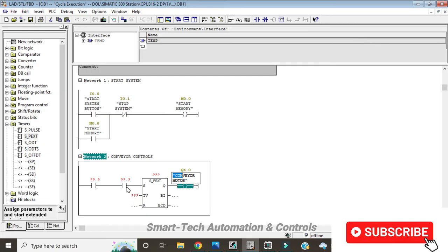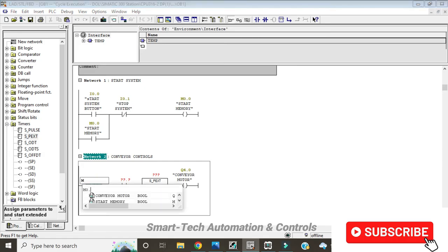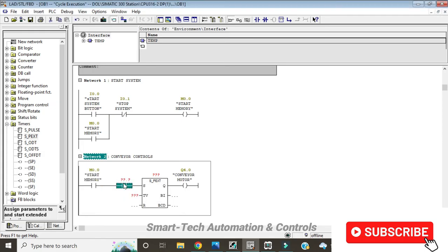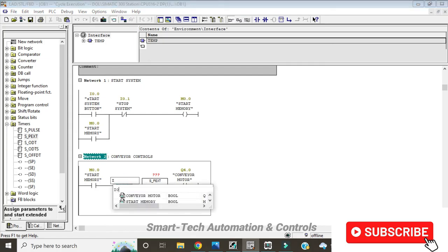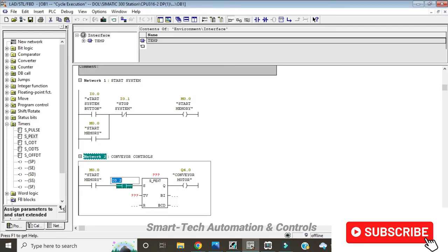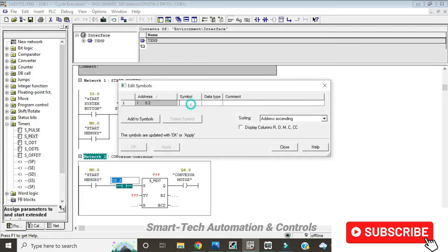These two normally open contacts will be the conditions which must be fulfilled before the timer gets activated and the motor starts. The first condition here will be the start memory. That means that the start memory coil here must be at logic 1, meaning the system must be on. And so here we shall give it address M0.0 for the start memory. Then for our second normally open contact, this will be the sensor that must detect that there is a product. Therefore, we shall give it address I0.2. And for the symbol, we can call it sensor.